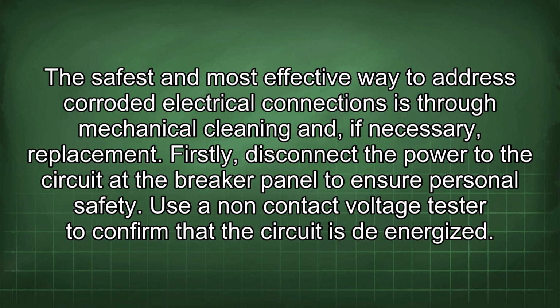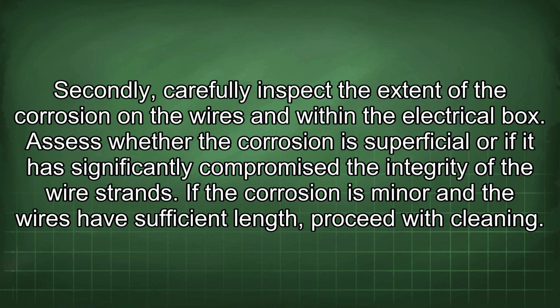Firstly, disconnect the power to the circuit at the breaker panel to ensure personal safety. Use a non-contact voltage tester to confirm that the circuit is de-energized. Secondly, carefully inspect the extent of the corrosion on the wires and within the electrical box. Assess whether the corrosion is superficial or if it has significantly compromised the integrity of the wire strands.